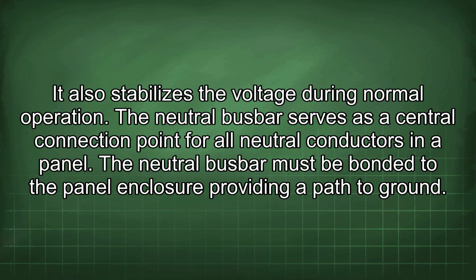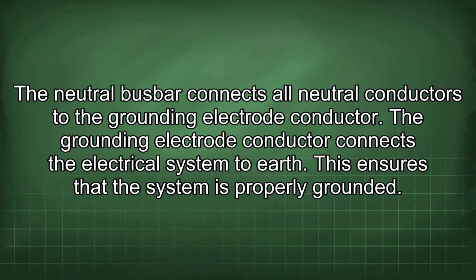The neutral busbar serves as a central connection point for all neutral conductors in a panel. The neutral busbar must be bonded to the panel enclosure, providing a path to ground. The neutral busbar connects all neutral conductors to the grounding electrode conductor. The grounding electrode conductor connects the electrical system to earth. This ensures that the system is properly grounded.